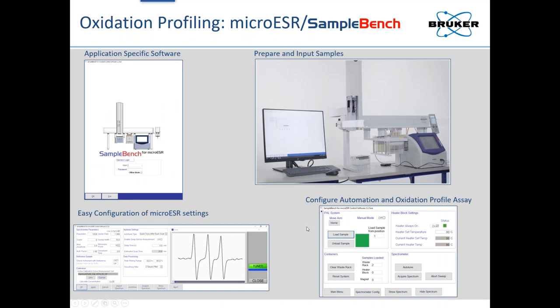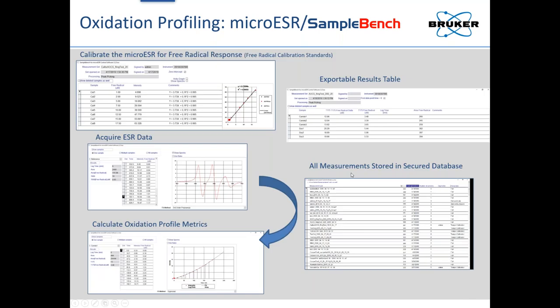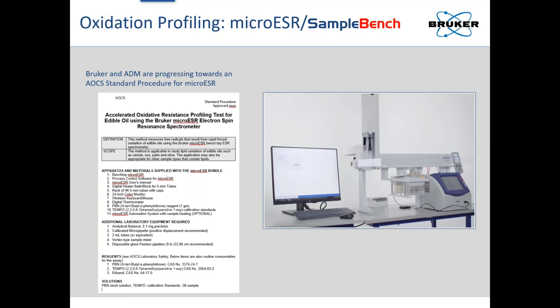The product we've developed over the last year is a very simple, very portable electron spin resonance spectrometer with a very small magnet. We've developed software specific for running this oxidation test, and also provided a robot for higher throughput than putting samples in manually. We're currently working on getting a standard procedure from AOCS, hoping to get that through this fall and take it further. I'll now turn it over to Professor Toski, who will show some more specific use of this with olive oil measurement.